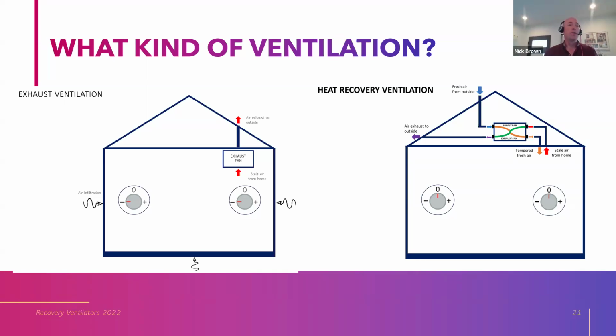Here's the first diagram I'll show you. They're pulling in fresh air from outside. That could be up, down through the roof or in through a wall, lots of different ways to accomplish that. Then it's running that fresh air from outside through a filter in the recovery ventilator box. And it's bringing that tempered fresh air into the house. That's the orange arrow. At the same time, it's pulling stale air from the home. And although the airstreams never cross, they swap heat. Okay, that's a heat recovery ventilator in that heat exchanger core. And then that stale air gets taken outside.